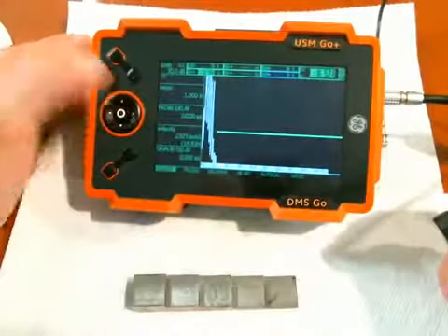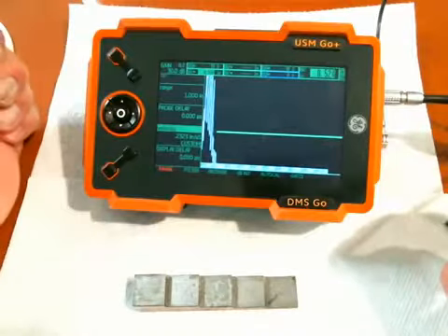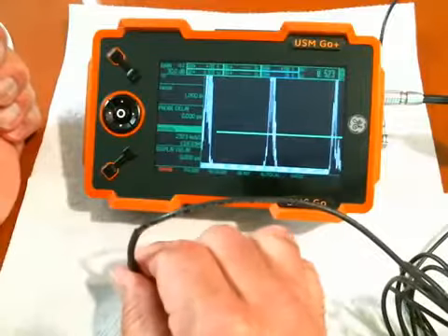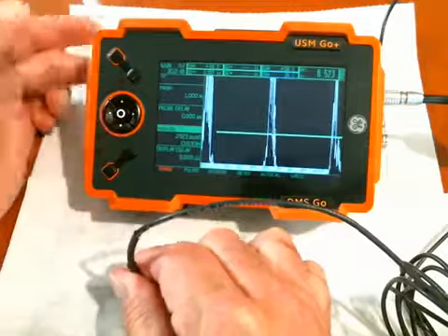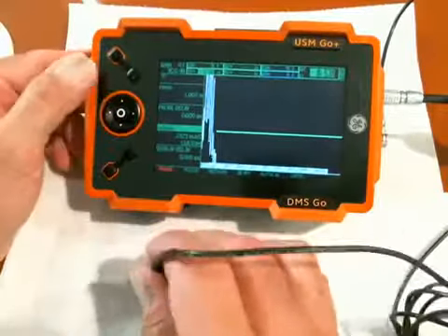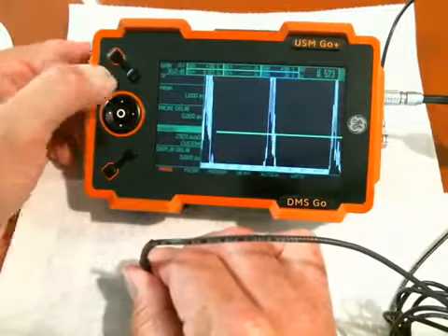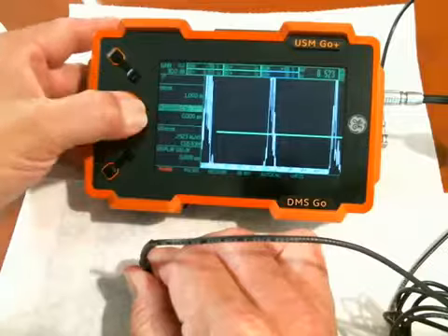Okay, now I have set my velocity to common velocity for steel, 0.2323. And I notice, like I say, my 1/2 inch is showing 0.523. That means that I have a little bit of probe delay that is adding into the sound path. So the protective face of the probe, the coupling layer, things like that are conspiring against me to make the reading thicker than it actually is.